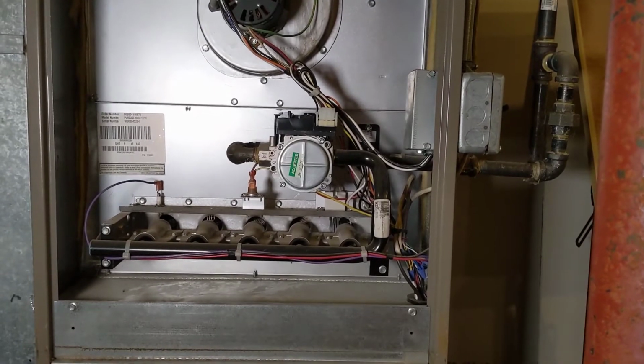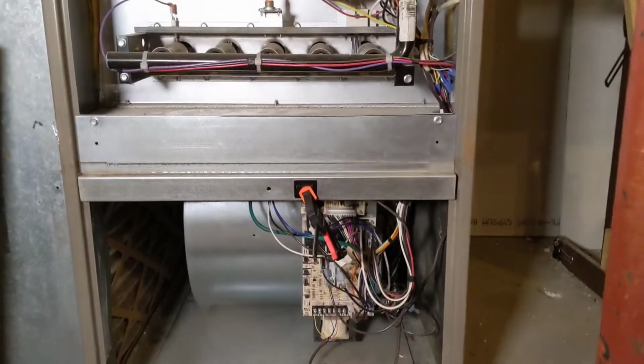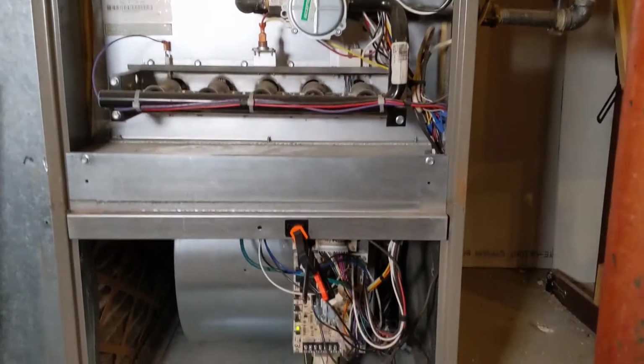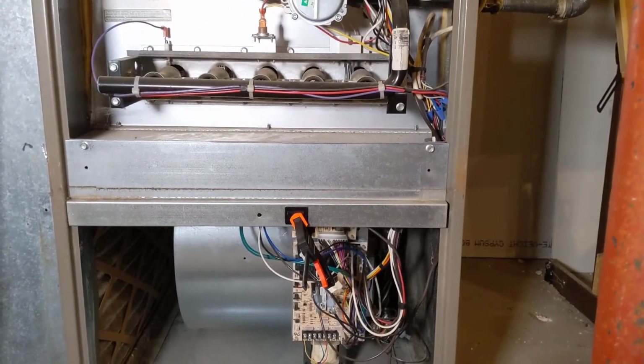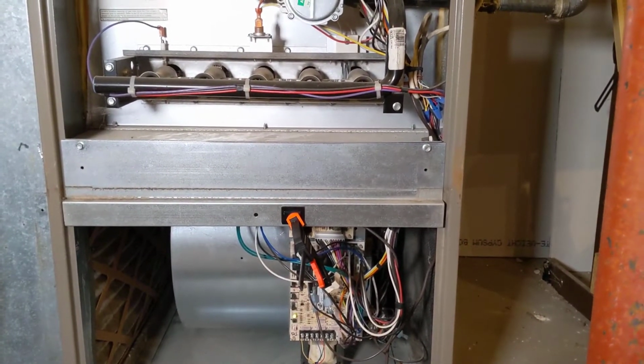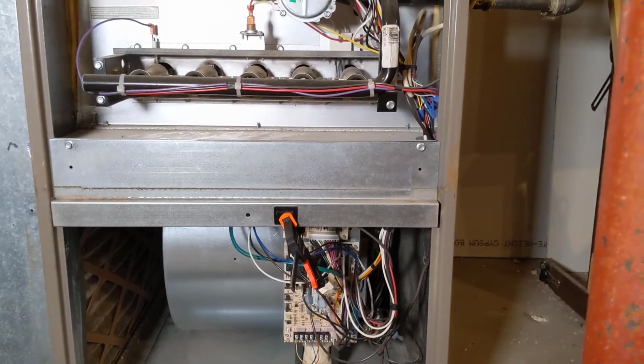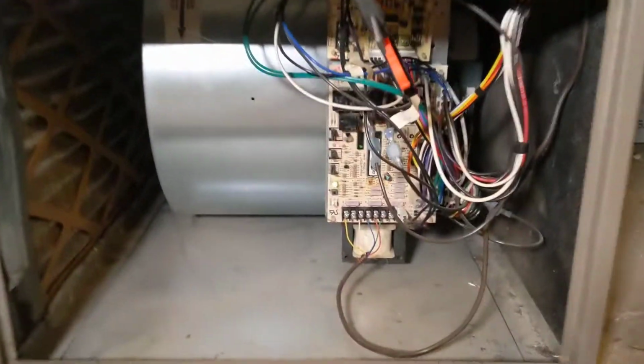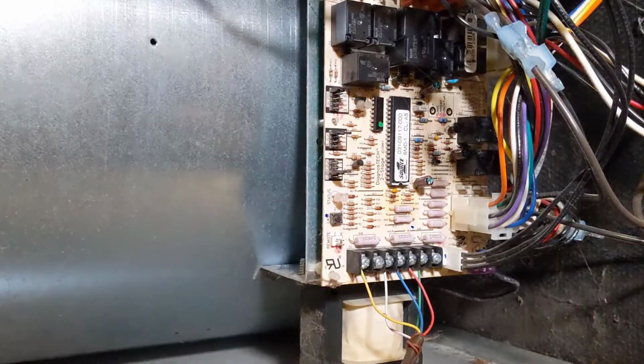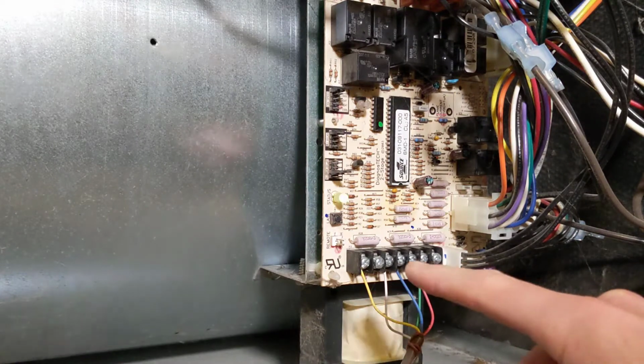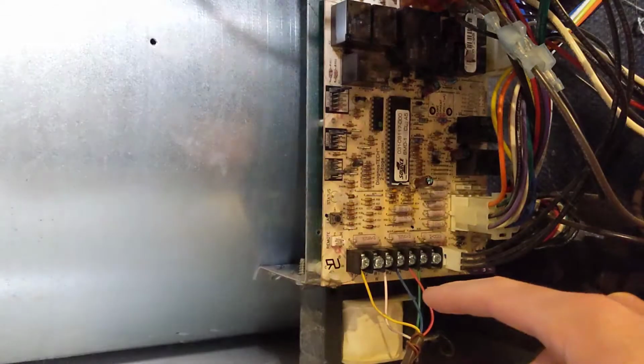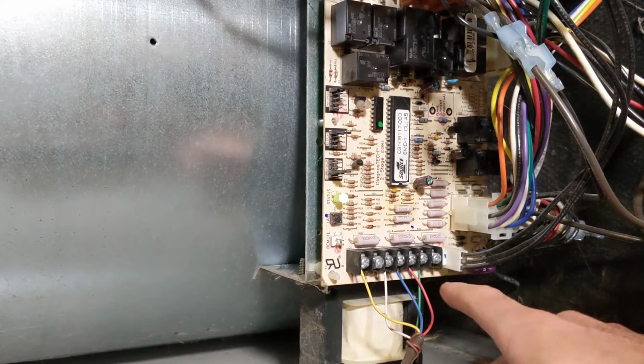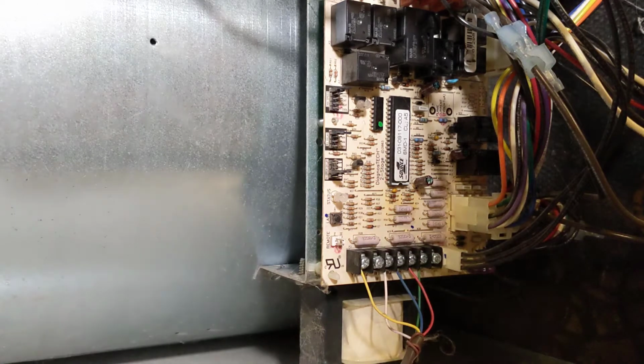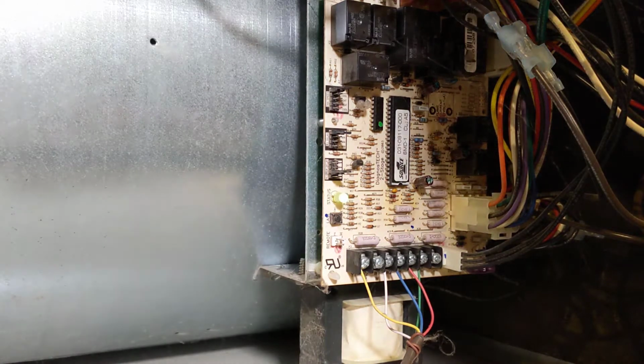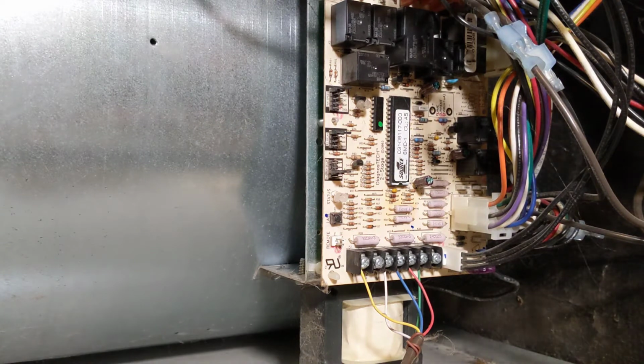If that's all true and the furnace is still dead like it is now, then what we could do is test to make sure, or confirm, that it is in fact our thermostat that's not working. So the way we do that is we're going to focus down here on our board. See this grouping of wires here? These are your thermostat wires. There's going to be letters next to each of these terminals here, and typically wire color also to kind of give away what these should be.